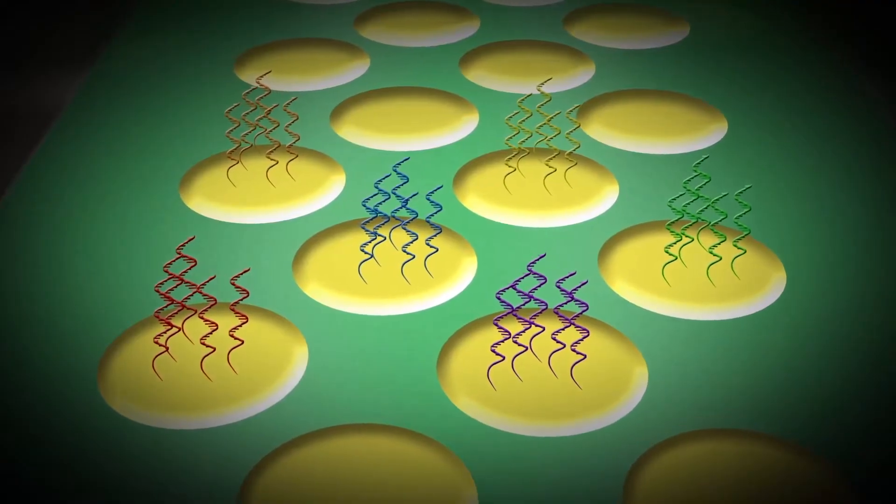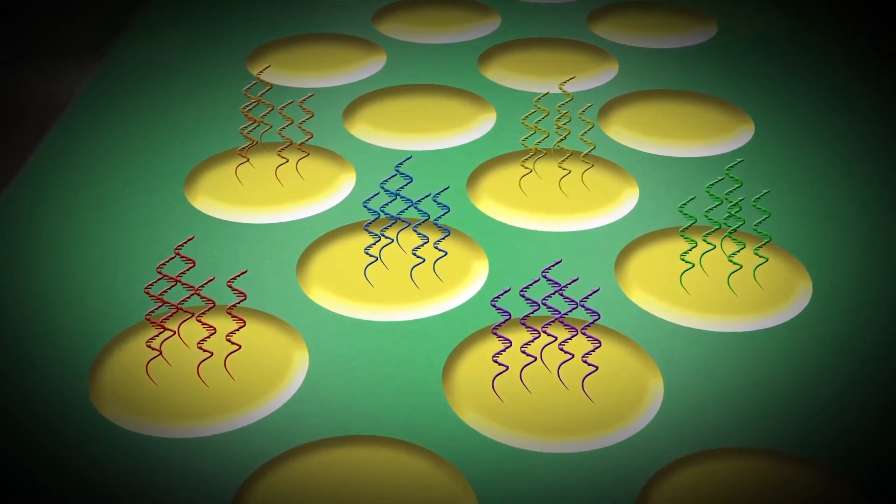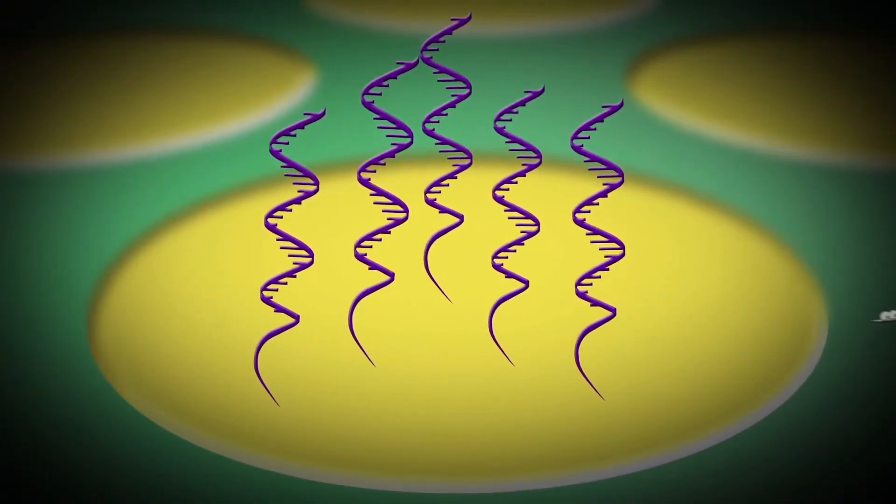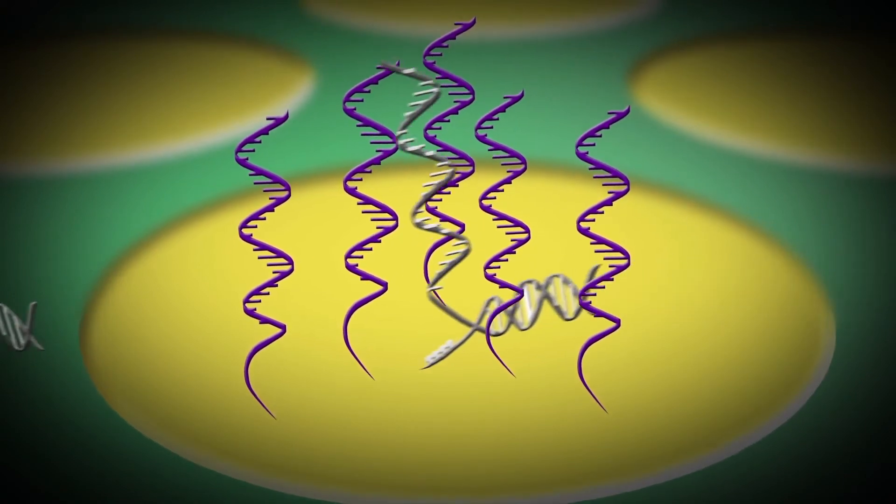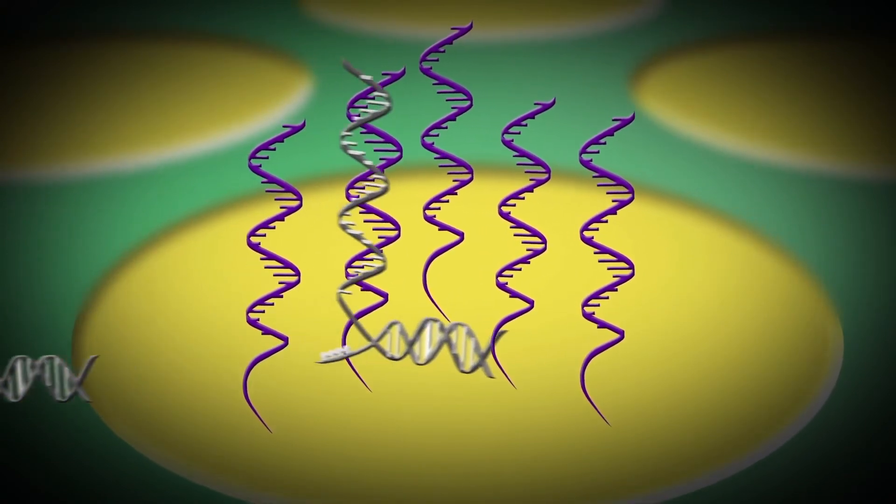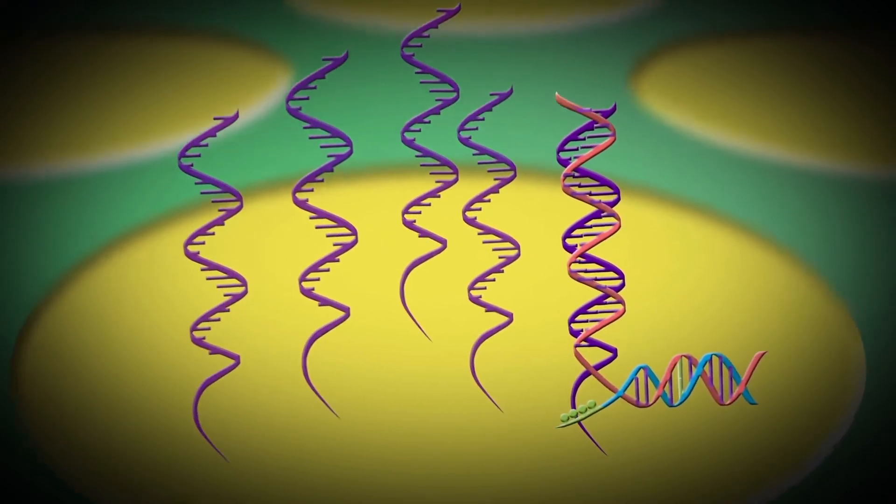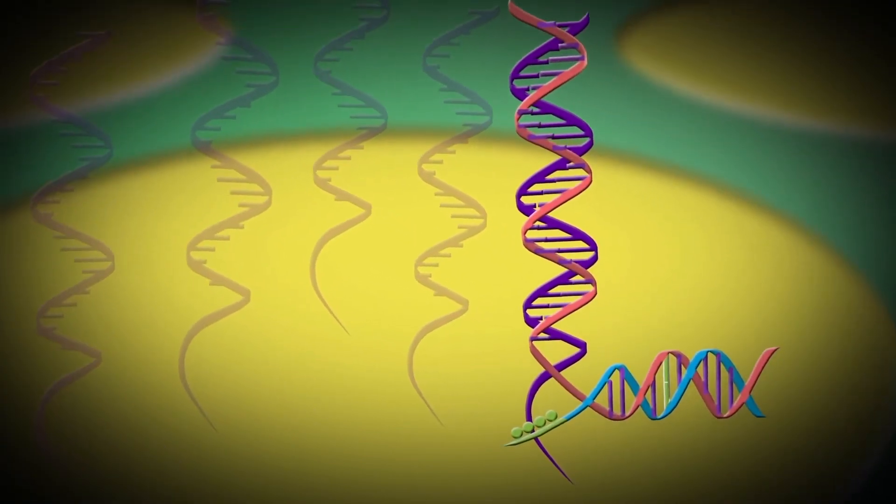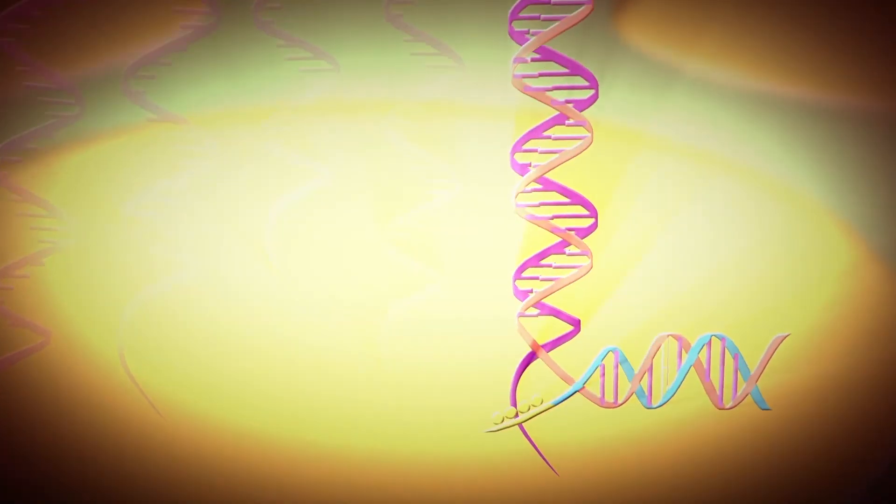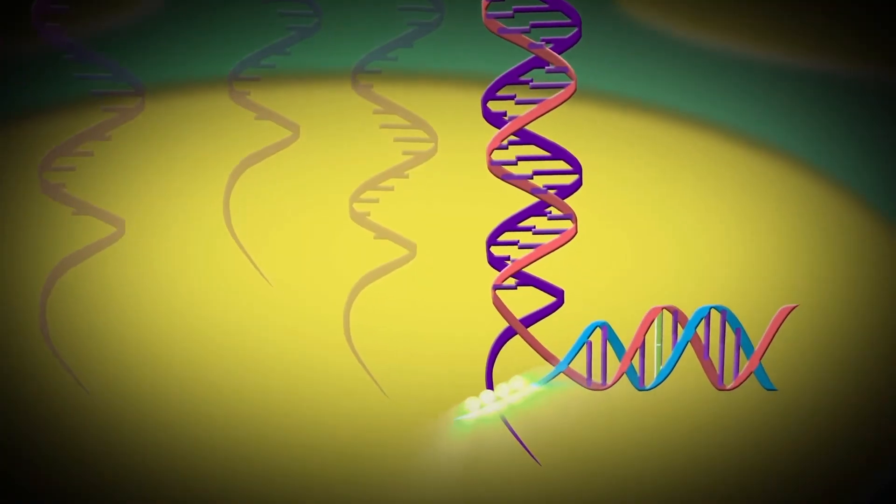Another unique and enabling aspect of the ePlex system is Genmark's proprietary electrochemical detection technology known as eSensor. With eSensor detection, sequence-specific capture probes bind both the target amplicons and the ferrocene labeled signal probe. When the sandwich of capture probe, target sequence, and signal probe complex is formed on the electrode surface, the ferrocene label generates an electrical current that is detected by eSensor, indicating a positive signal.